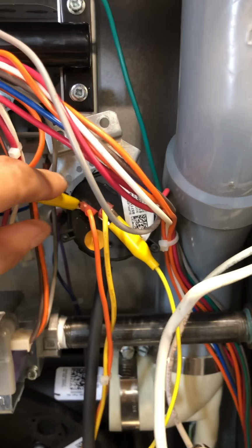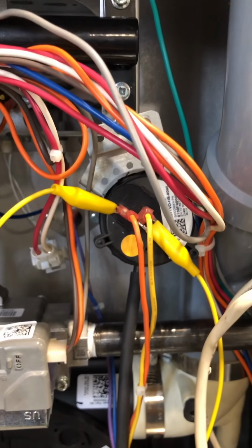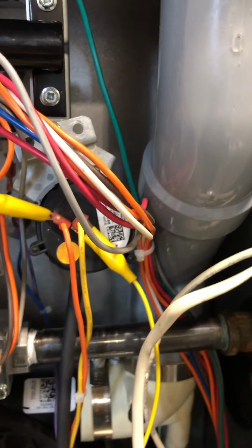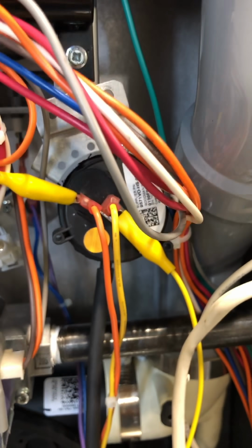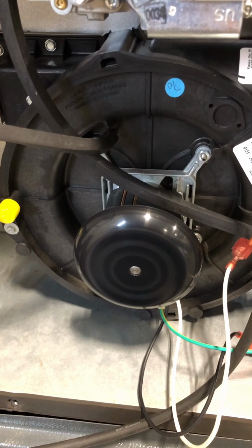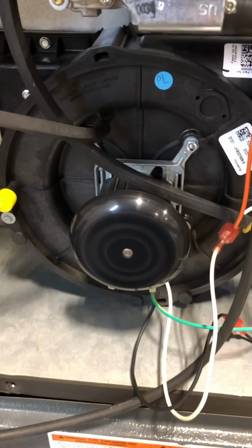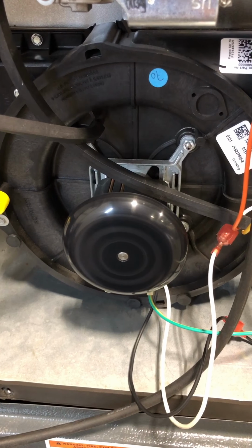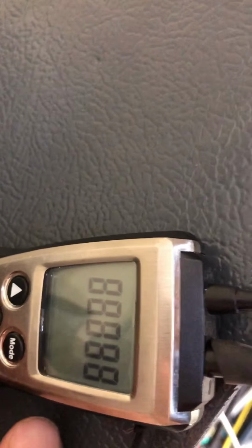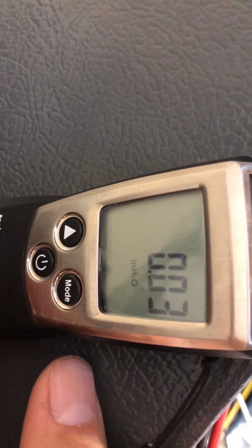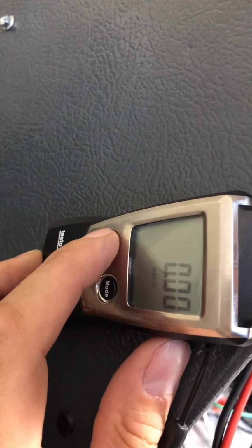Now let's see what happens as soon as I pull this jump wire, because that switch is technically open, I'm just bypassing it by jumping it across. Let's see what happens. Well, what do you know? Now the board has verified that it opened, now it will continue the process. Start the inducer. Switch is closed. I can verify that by my meter, it zeroed out. One second.